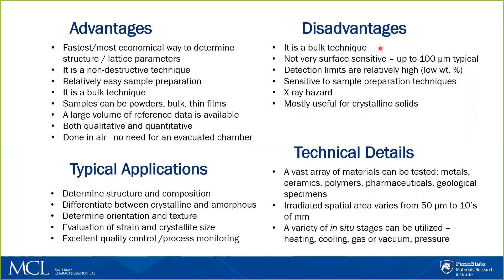I also list the fact that this is a bulk technique under a disadvantage, because if you really need to look at a small area of your sample, this can be challenging with this technique, particularly on a conventional powder diffractometer. It is not a surface-sensitive technique. We are typically penetrating up to about 100 microns, and your detection limits will be relatively high. We generally need low weight percents of a particular material to be present before we can detect it. It is highly sensitive to sample preparation technique, and if sample preparation is not done correctly, the analysis can be difficult, if not impossible, to analyze.